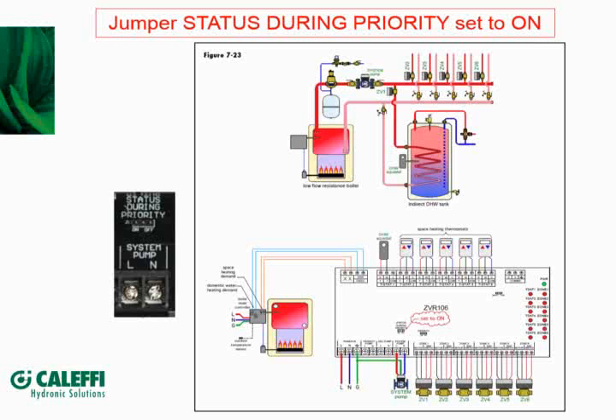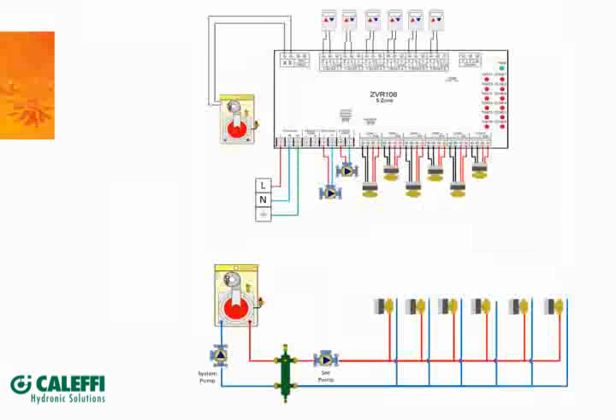Okay, another question. We only got 10 minutes here, but I think we're pretty close to the end. I take it from the opto relay that the zone valve motors outputs are Triac. Doesn't have to be a Triac. No, the optical is only on the feedback. Is only on the end switch. Oh, okay. But on these other ones, you're basically passing through. You're passing through your thermostat down on here, and then there's a relay in here to hold off the other zones. But the optical is on the feedback coming back.